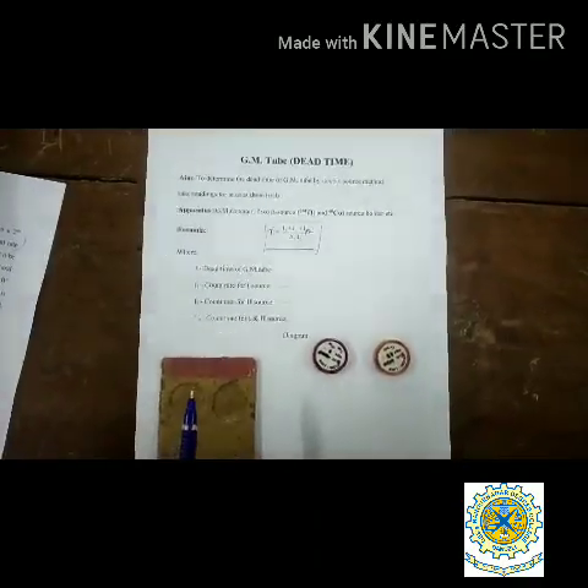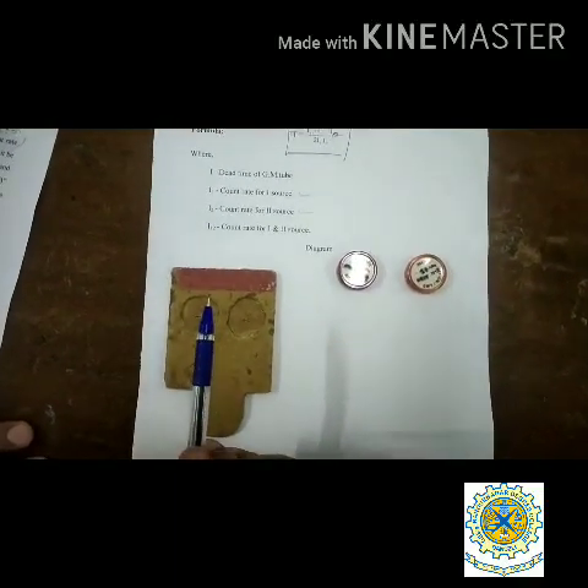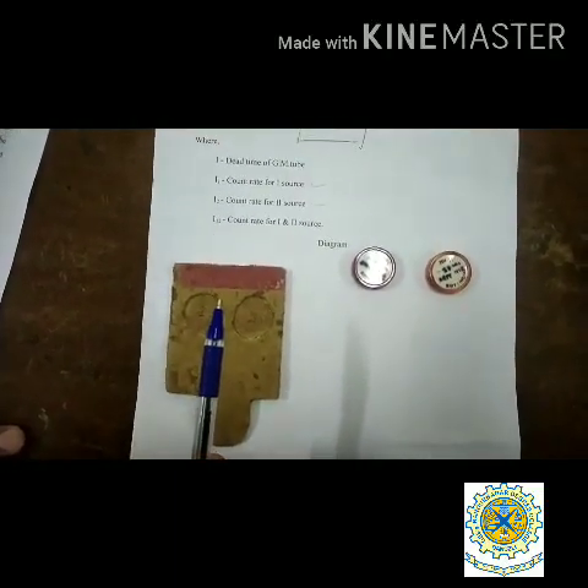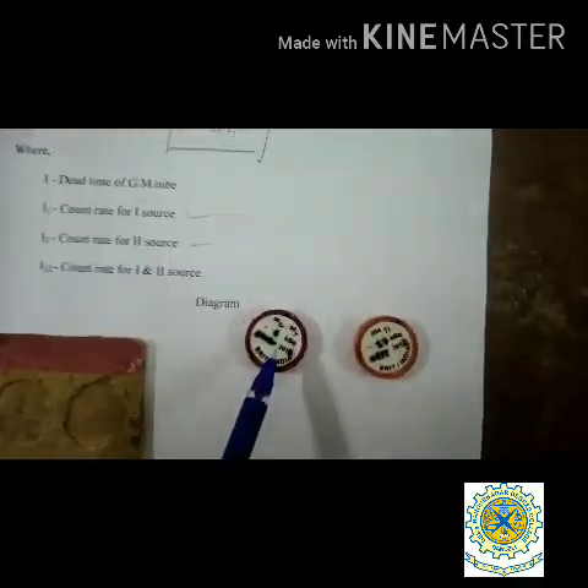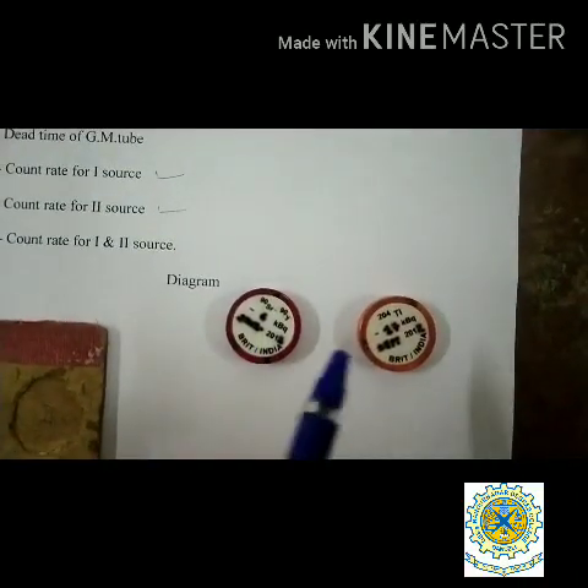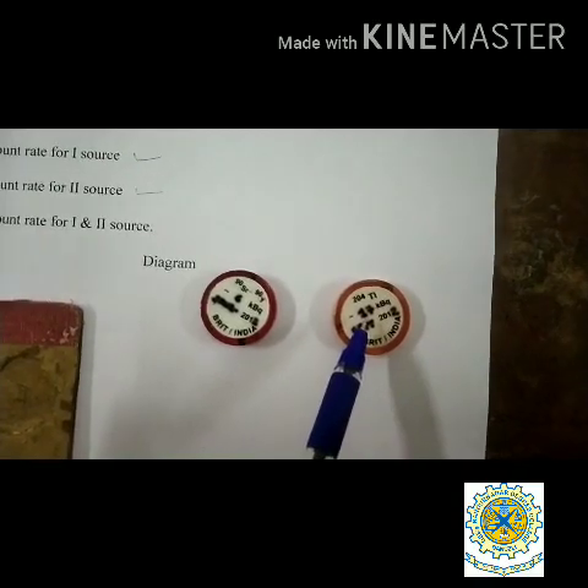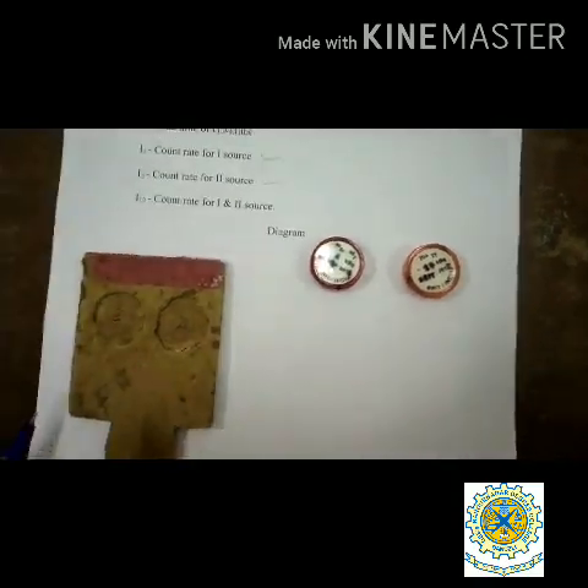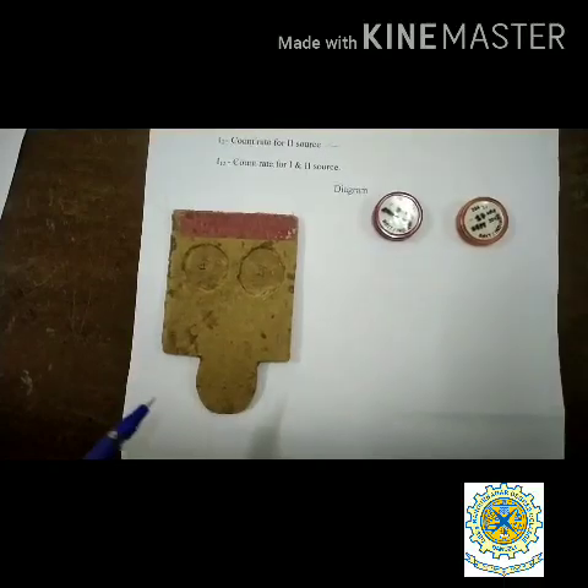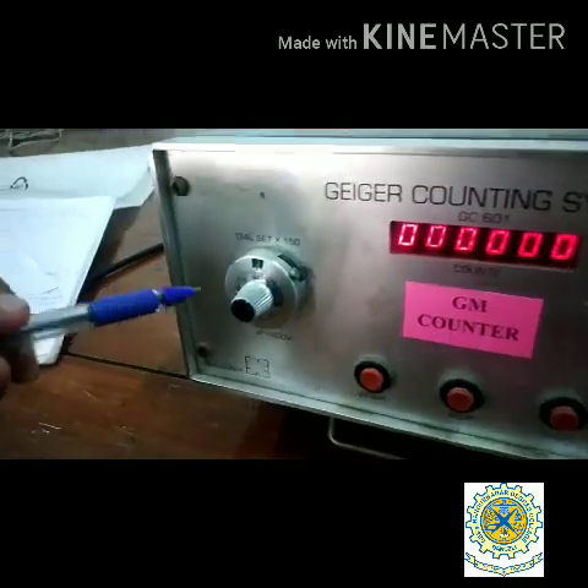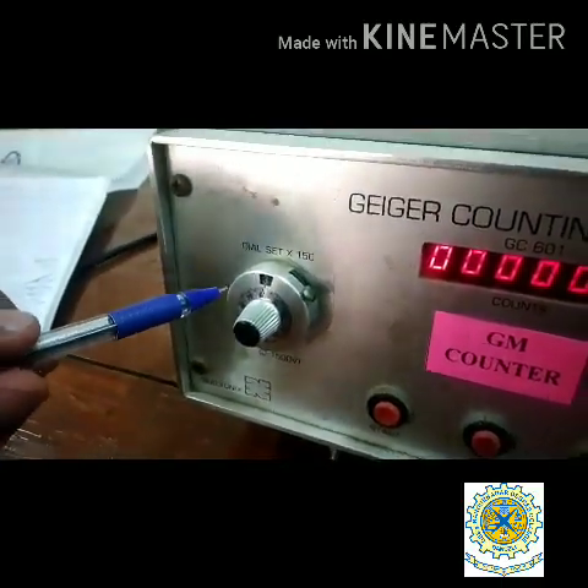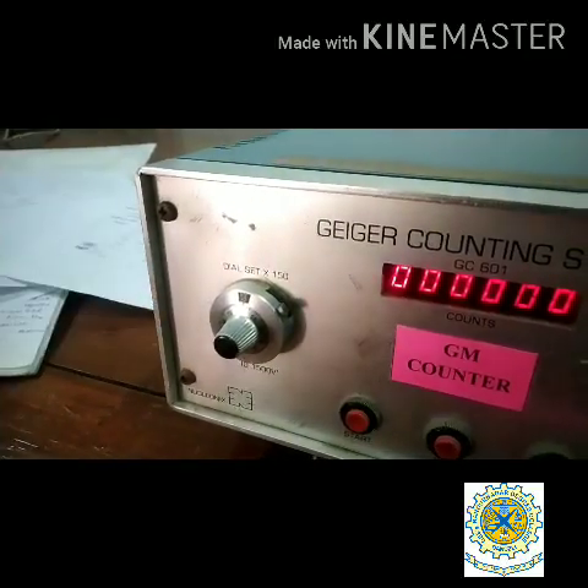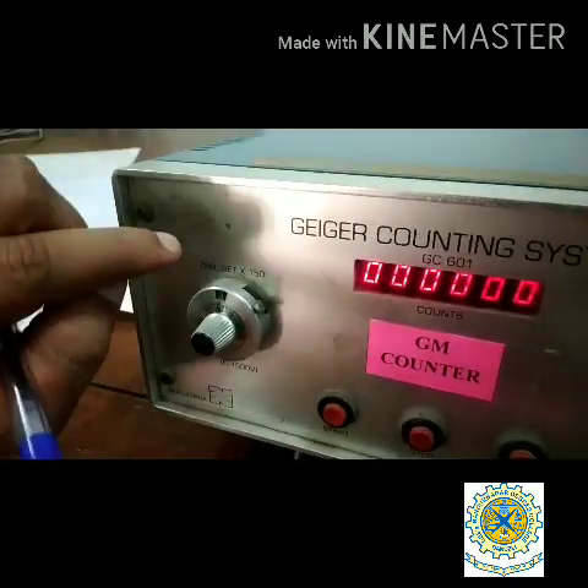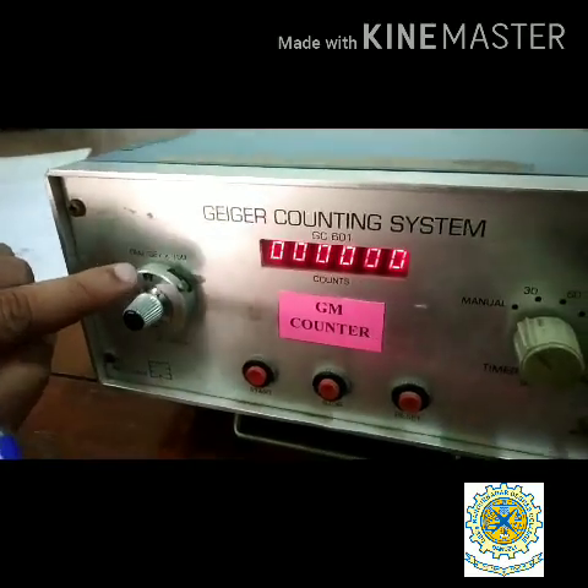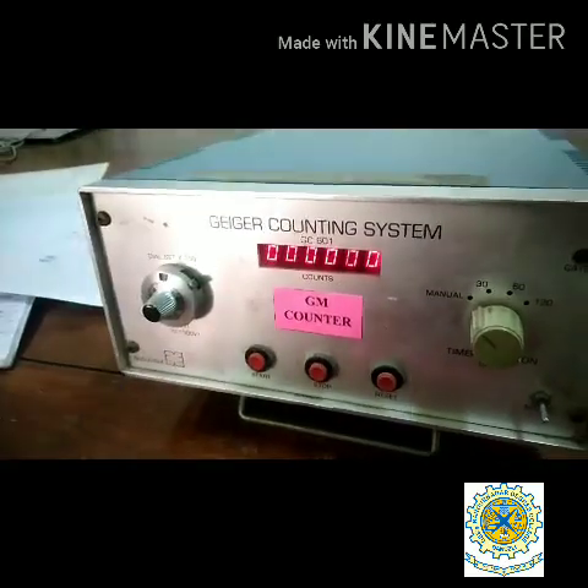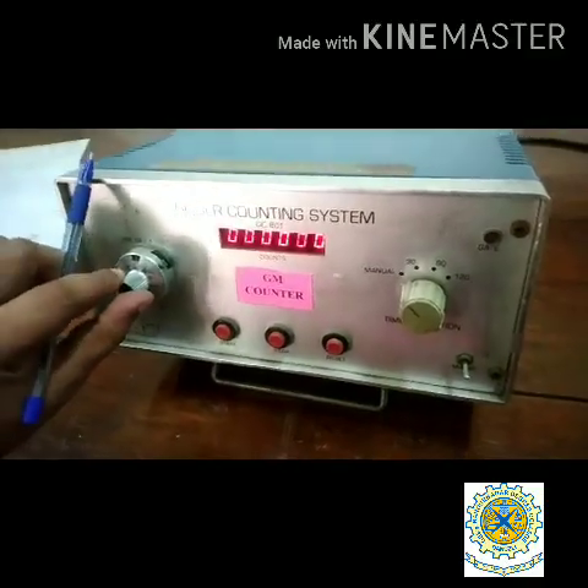For the procedure, as we are finding the dead time, we are using the double source method. In our studies, we are using strontium 90 as one source and thallium 204 as the other source, and this is a holder which has to be taken for our study. The operating voltage of this instrument is 540 volts, so I have set the dial to 3.6, which multiplied by 150 gives 540 volts.